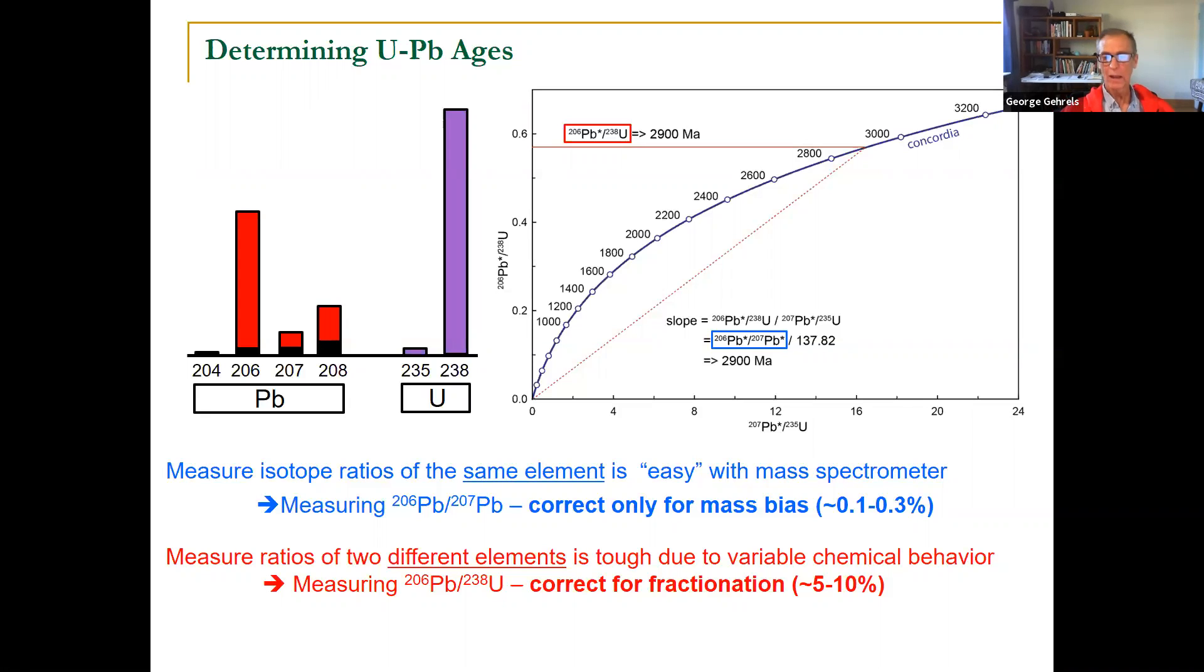Just a slight difference in mass. So the measured value off the mass spectrometer, 206-207, is very close to the true ratio. You might have to do a correction of a tenth of a percent or a third of a percent. We call this the mass bias correction.